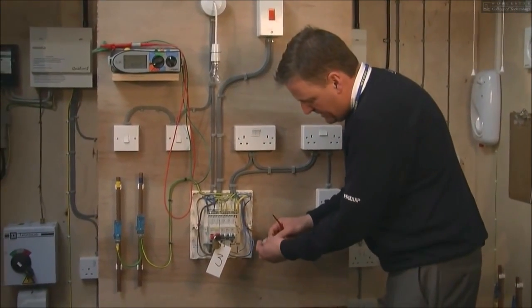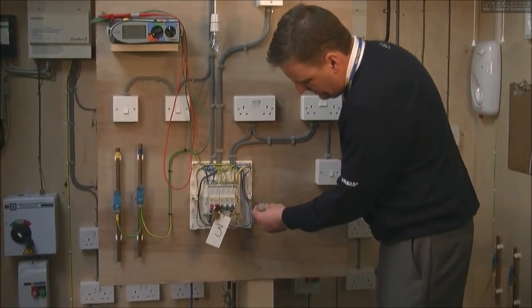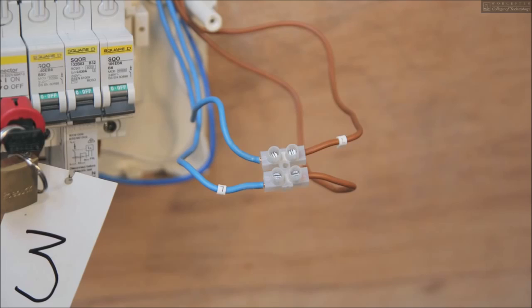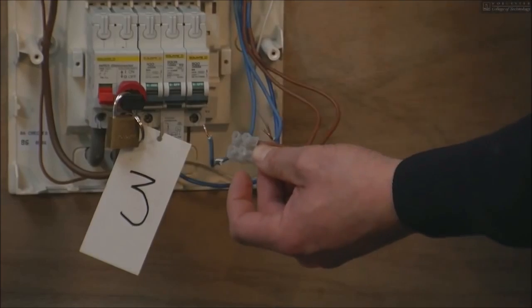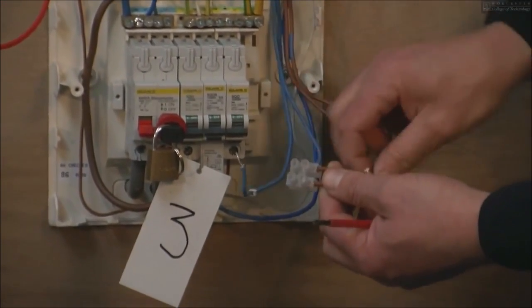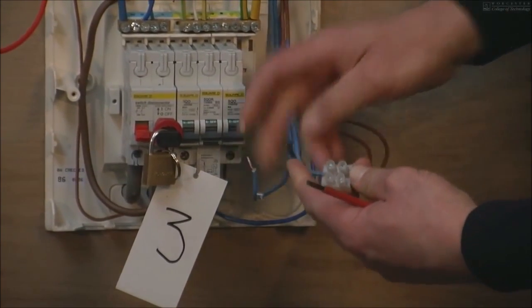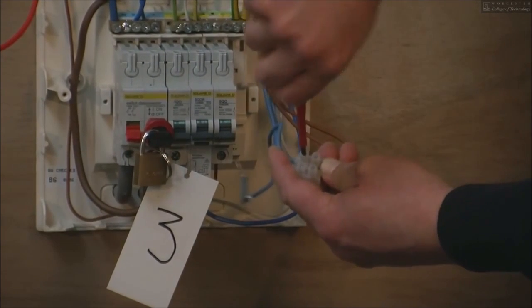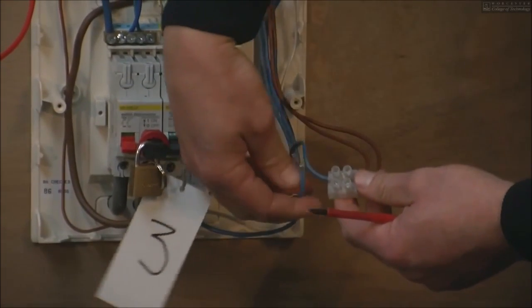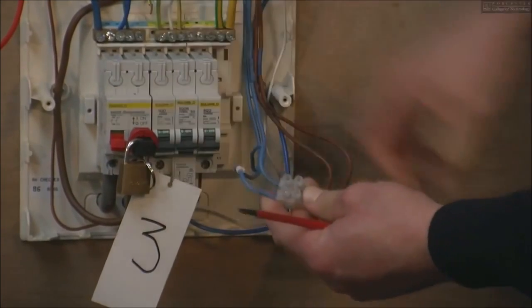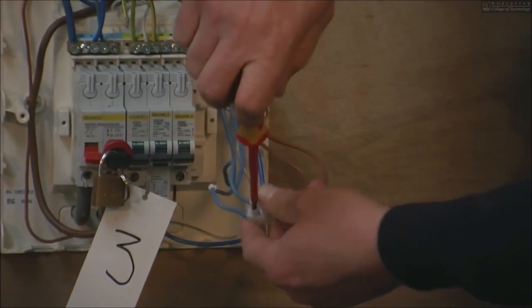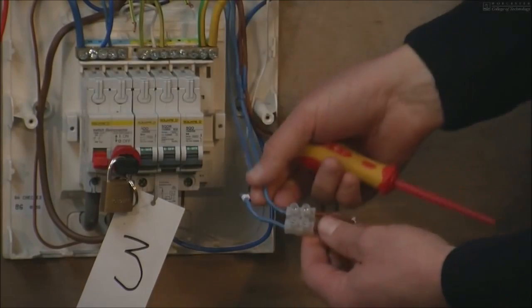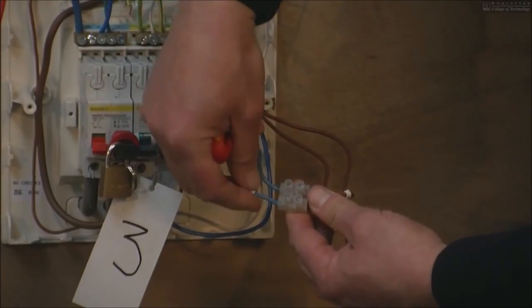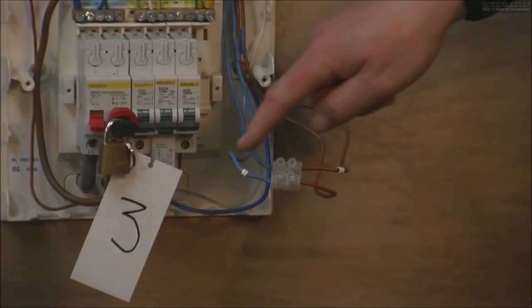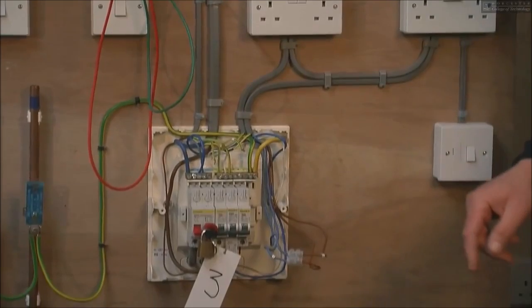The next part of the test is we're going to place the conductors now into a connector block. If you look hard enough onto the actual conductors, you'll see that they actually have markers on them. This is indicating the longest and the shortest leg. So what we do is we place the longest leg with the shortest neutral. The shortest line with the longest neutral, like so. As you can see, two longest legs are opposing each other. So what we've actually done now is we've made a continual circle through the installation. And this is also known as the figure of 8 connection.